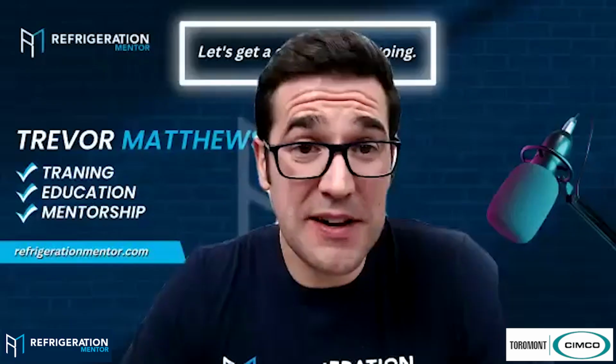I don't know if you remember, but I saw in one of the booths an ejector that was about that big and that long. And that was for a heat pump. I think it was a 2.5 megawatt heat pump, and the ejector was specially made for that. And you start reading and looking at it, and you see that they are achieving a COP in excess of 3 or 4 using a CO2 heat pump at very high temperature. And that's what's exciting about it.